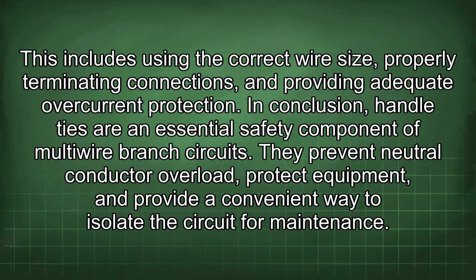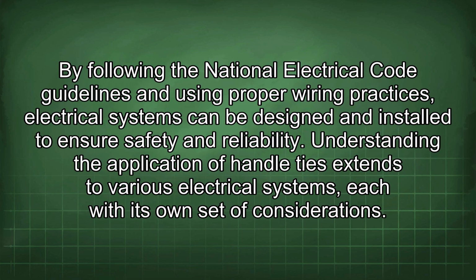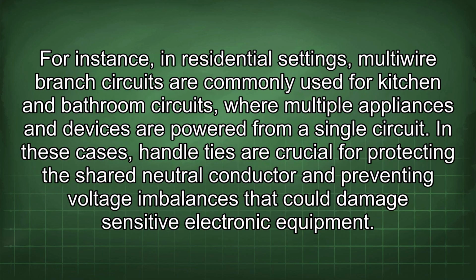In conclusion, handle ties are an essential safety component of multi-wire branch circuits. They prevent neutral conductor overload, protect equipment, and provide a convenient way to isolate the circuit for maintenance. By following the National Electrical Code guidelines and using proper wiring practices, electrical systems can be designed and installed to ensure safety and reliability. Understanding the application of handle ties extends to various electrical systems, each with its own set of considerations. For instance, in residential settings, multi-wire branch circuits are commonly used for kitchen and bathroom circuits, where multiple appliances and devices are powered from a single circuit.